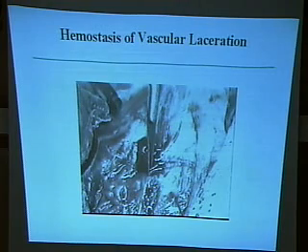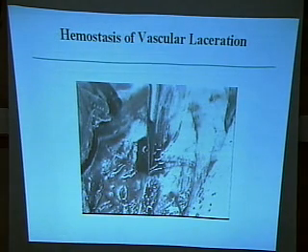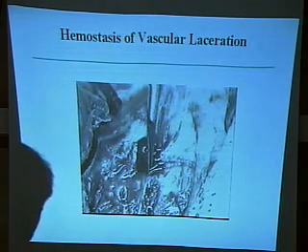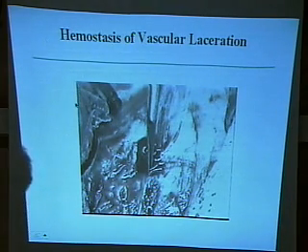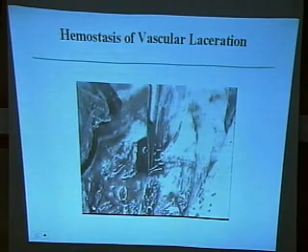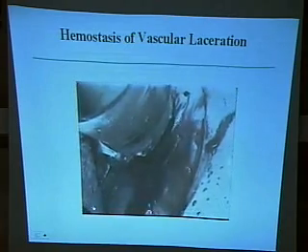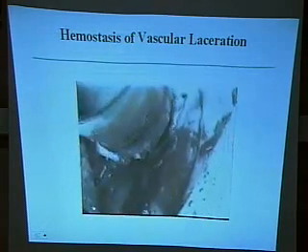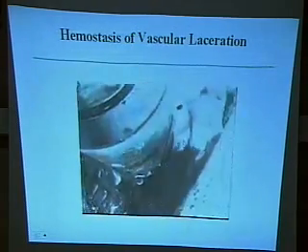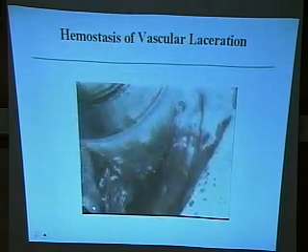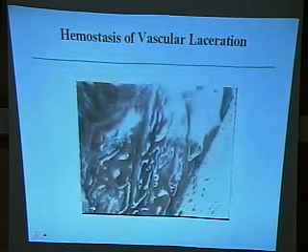So we actually connected the HIFU transducer to a mechanical scanning device with a frequency of about 20 hertz and an amplitude in the order of the incision length, about 7 to 10 millimeter. And that's what you're going to see. Okay, here we go. So we didn't quite see the start of the bleeding. Significant bleeding there because it's a laceration. You can see the blood still coming out. HIFU treatment, and then no bleeding.